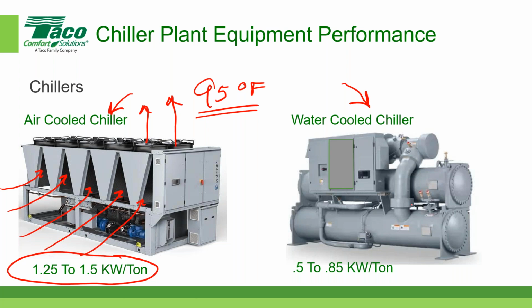Now, when we talk about water-cooled chillers, let's assume for a moment this is the compressor here. This is probably the condenser down here. We're rejecting heat to condenser water. We probably have an entering condenser water of 85 degrees Fahrenheit and a leaving condenser water probably around 95 degrees Fahrenheit over here. By the way, if the air is coming into the air-cooled chiller at around 95, it's probably leaving up here anywhere from 10 to 15 degrees higher. Let's say it's 15 degrees, so that would be about 110 degrees Fahrenheit.